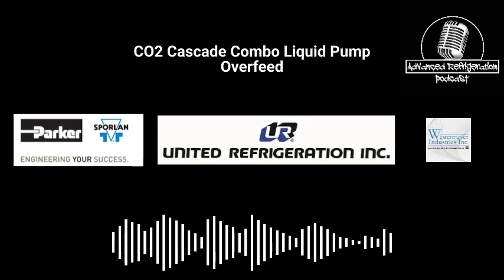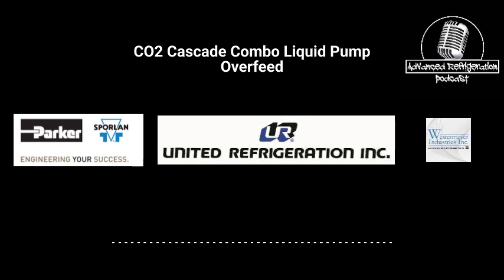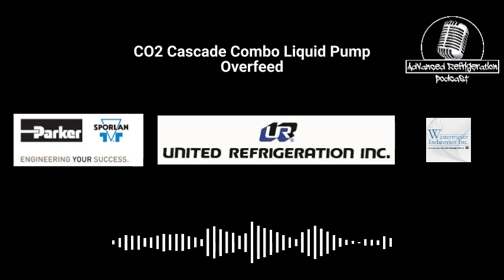One of the most common things with these systems is they're getting bound up with air. Someone got some non-condensables in there somehow, and the air is going to rise to the highest point. Usually those heat exchangers are the highest point. So there's usually, on the inlet side where the CO2 goes in as a vapor before it comes out a liquid, right there at the very tippy top, a service valve where you could blow some of that charge. So I see fewer issues with the Cascades doing that than the liquid pumped overfeeds.